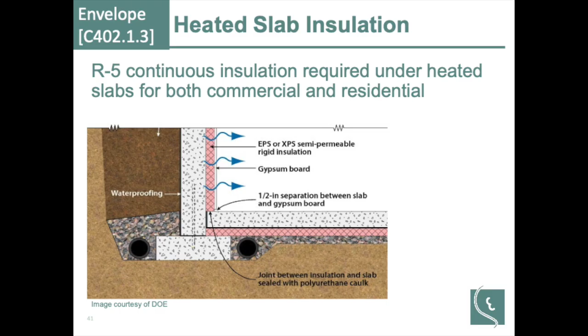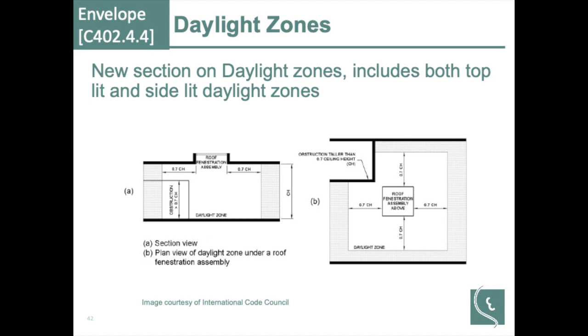For daylit zones, they've now broken this apart a little better, into top-lit and side-lit zones. Top-lit being from skylights, rooftop monitors, and things like that, with guidance as far as how large that zone is. These zones need to be labeled and marked on the prints. This is one example of how that might occur on the prints: a school building that has some perimeter windows. There weren't any skylights, but you can see where we've shaded from the window in, at the width of the window plus approximately 2 feet. These diagrams are actually directly in the code book, and they are also in the online version, including their graphics.